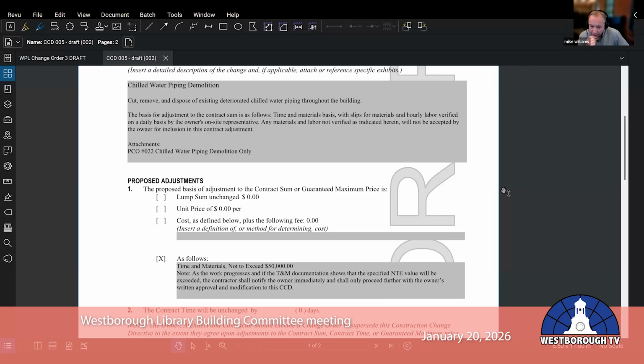To answer your first question, Pete, we have two parallel systems. The outside heat pump slash chiller reuses the piping planned to feed multiple units throughout the building. In addition, there are split systems that use just refrigerant piping, like in the IDF closet where we just need a cassette type wall mounted unit to address that space with higher heat loads. There are a couple other areas that will rely on refrigerant, but the chiller and chilled water piping is separate from that refrigerant system, and that goes throughout the building.